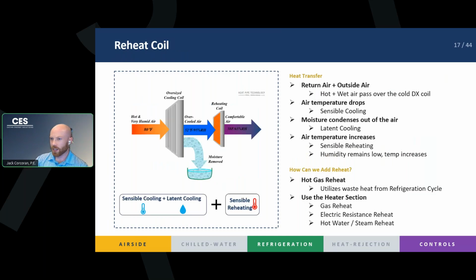And the next section you could have is a reheat coil, right? So in cooling mode, we mentioned that we get a lot of latent cooling just by having our coil temperature lower than the dew point. Many times you're going to have situations where the outside air volume is super high, right? And in the middle of the summer in New York, we all know it gets very, very humid. You're going to have to overcool your air, right? Or have your coil temperature be lower because the dew point of the air, you want to extract a lot of moisture. So you need to have a low coil temperature, right? But by having a low coil temperature, you're also going to overcool the temperature of the air, right? So you're going to be coming off at now 52 degrees Fahrenheit instead of maybe 55. And that's too cold to send throughout the space.